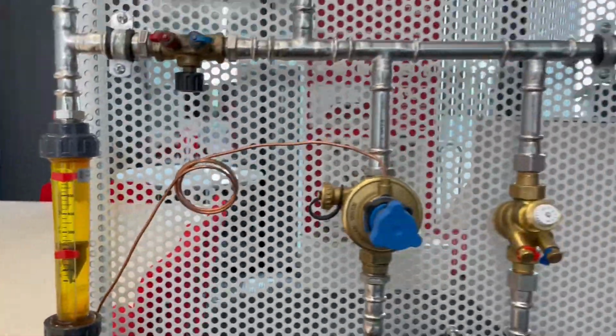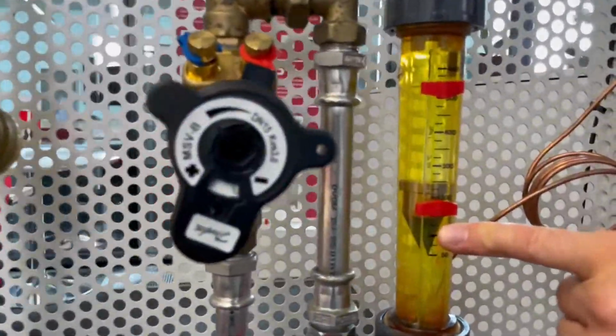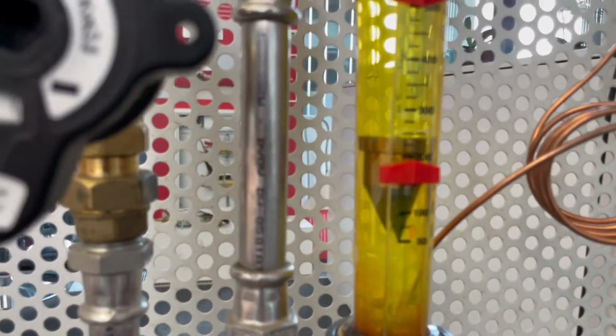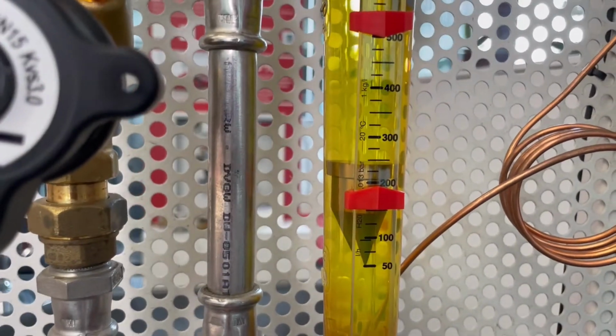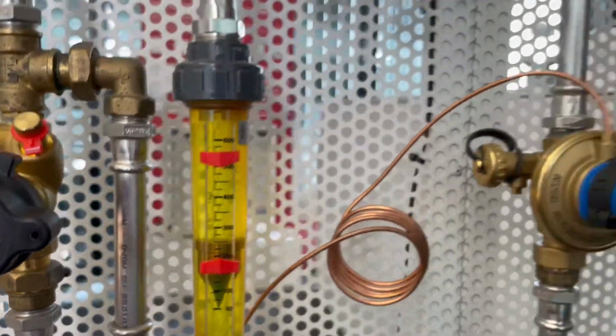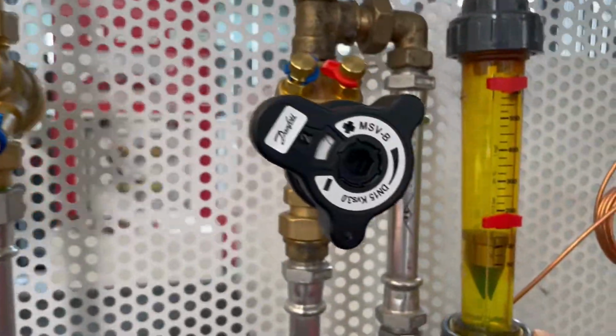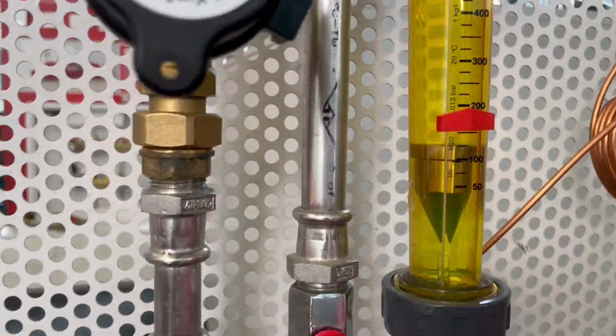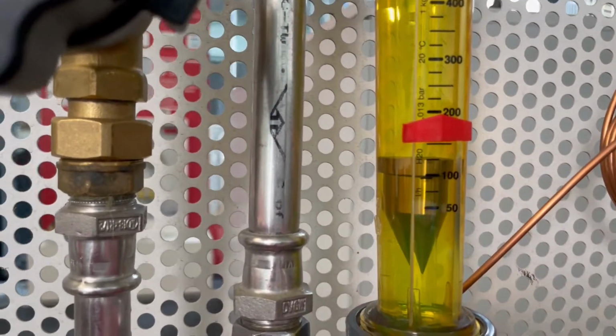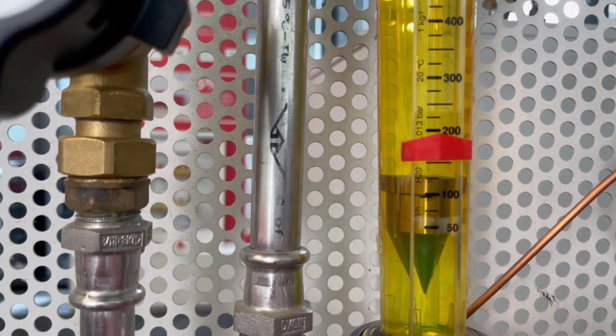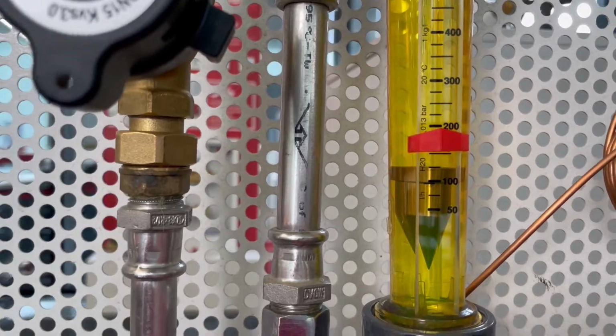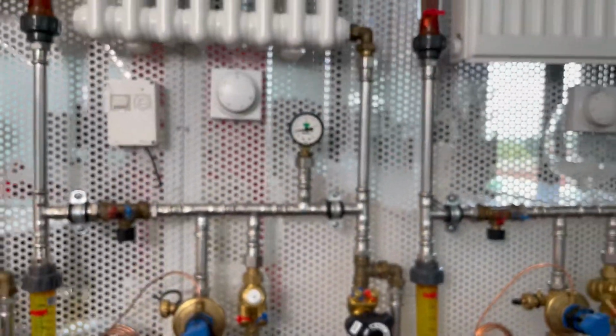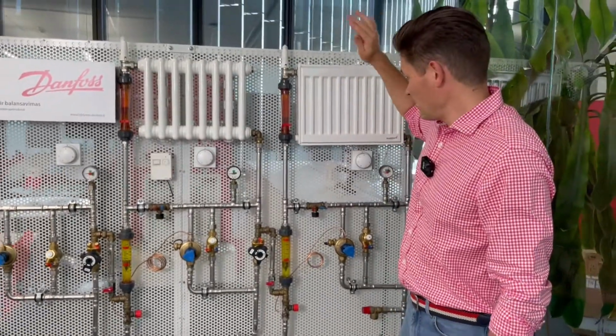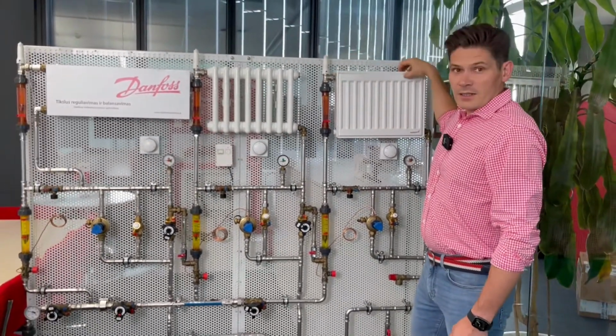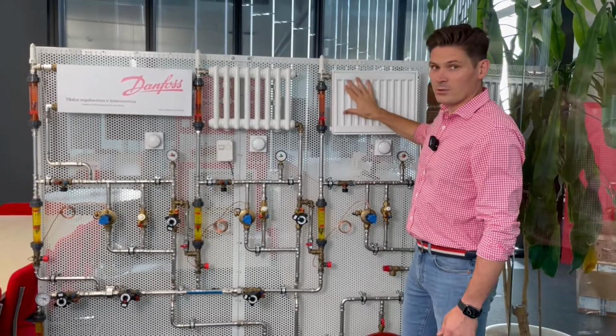Riser number 2, we have 230, 240 liters, also it is okay. And the last riser, which we squeezed, or which we just limited to 200 liters, is now getting 120 liters. People again are not happy. They call the maintenance company and say the top of the radiator is hot and the whole radiator is cold.